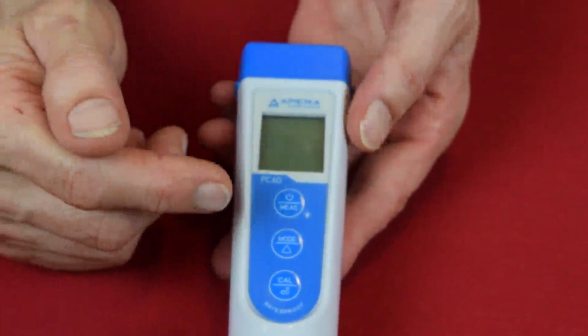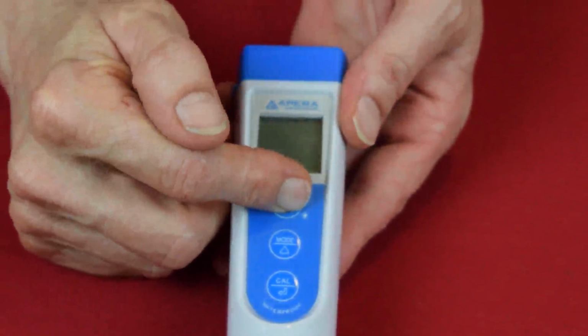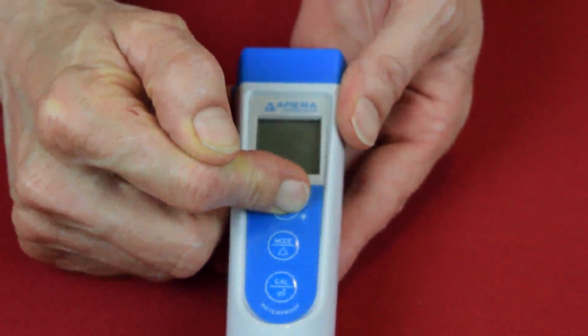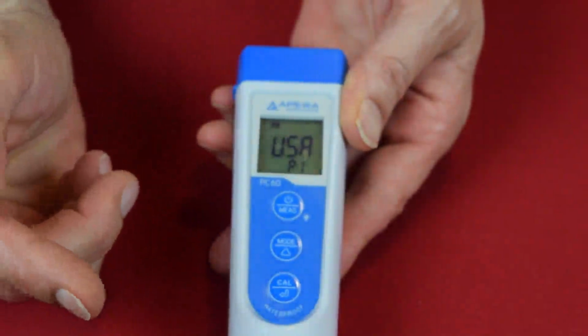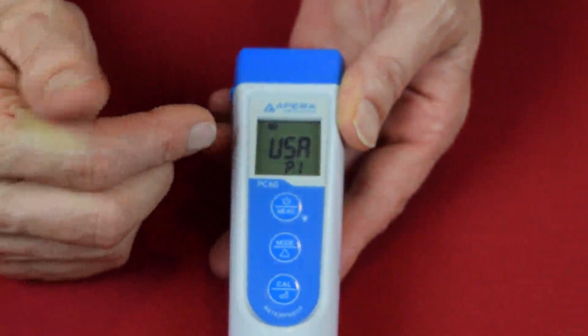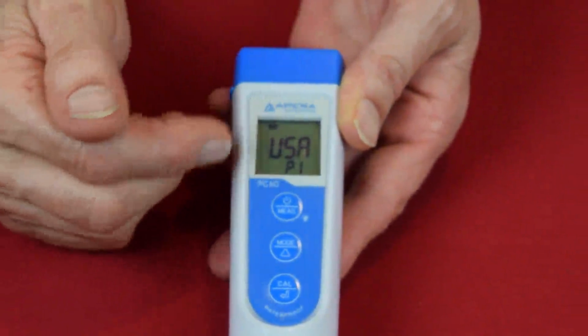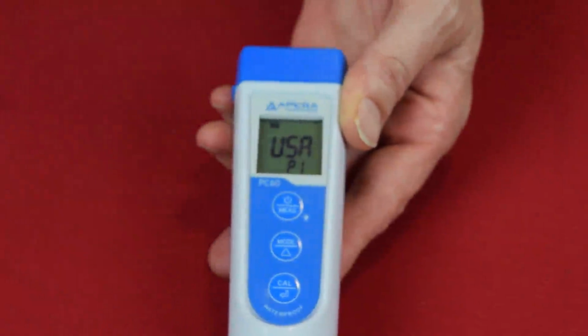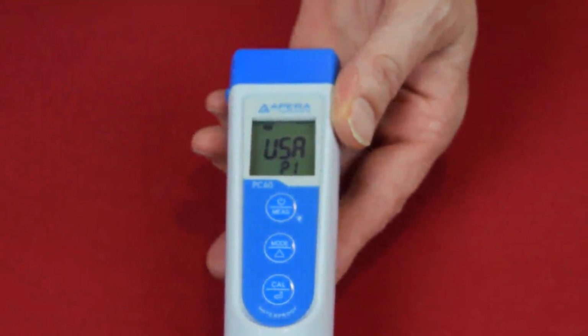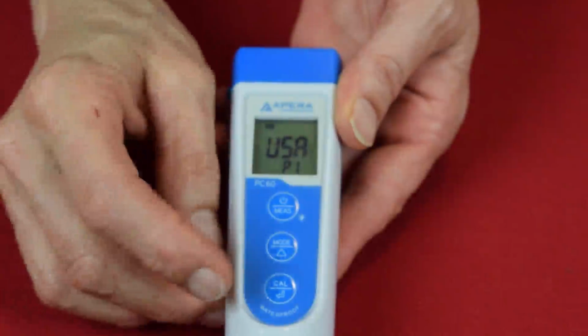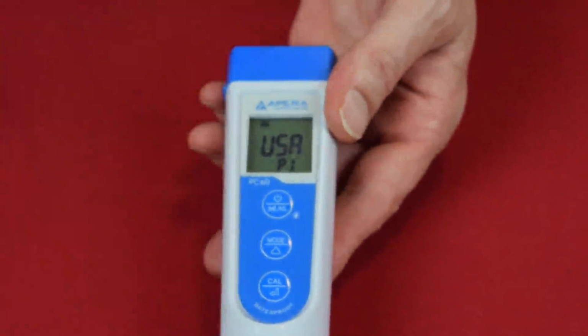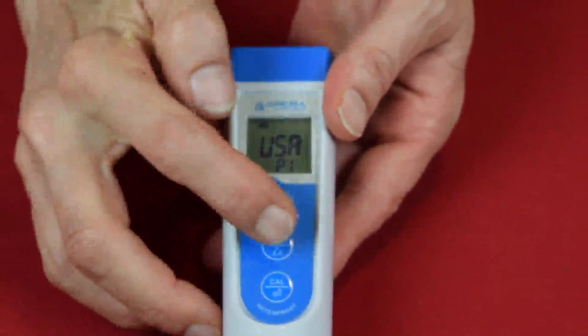Alright, so if I want to set some parameters, I press and hold down the measure button until it comes on. And now this starts me off, and I got 8 different ones, P1, P2, P3. P1 allows me to select the pH buffer, whether it's USA or NIST. And I press mode again.